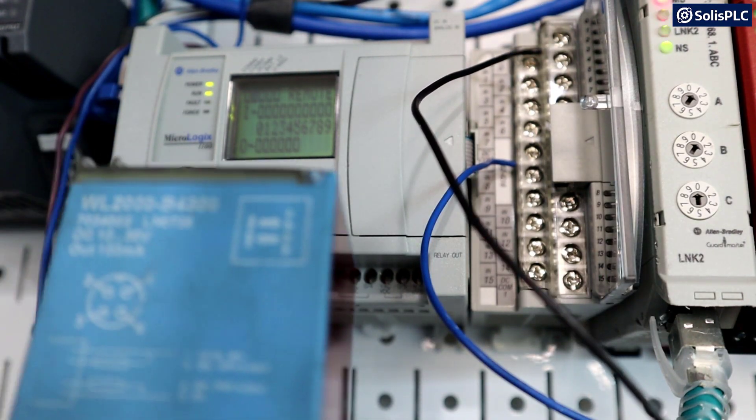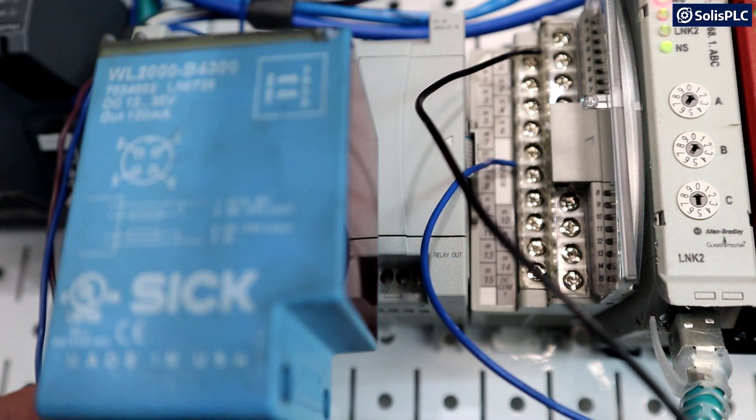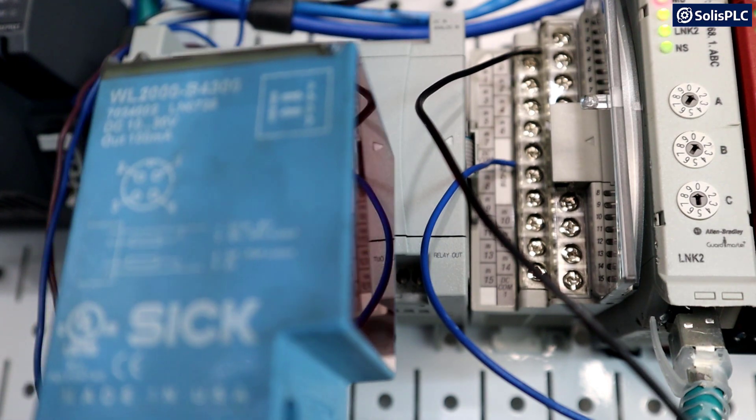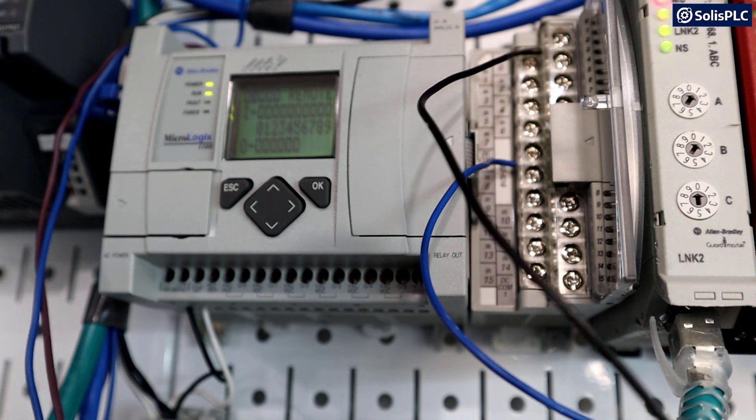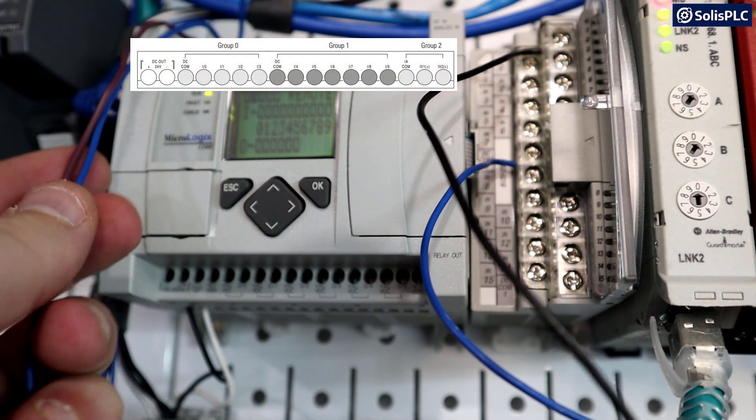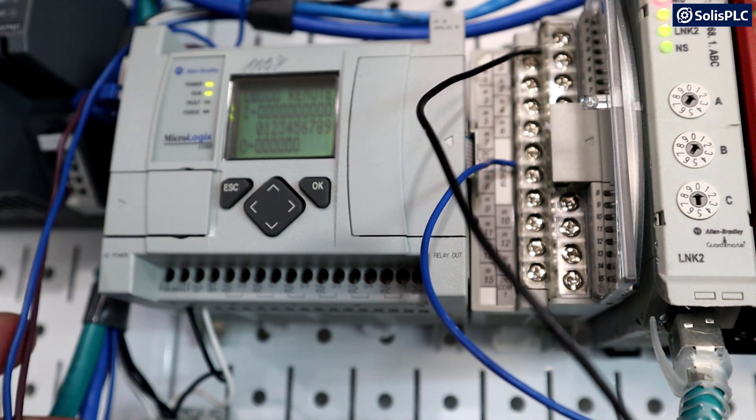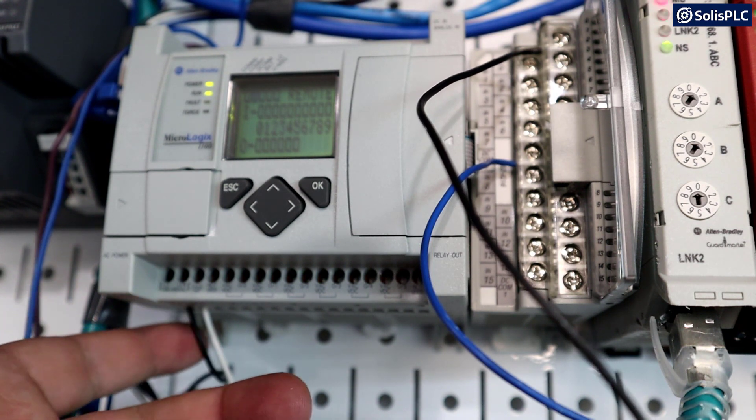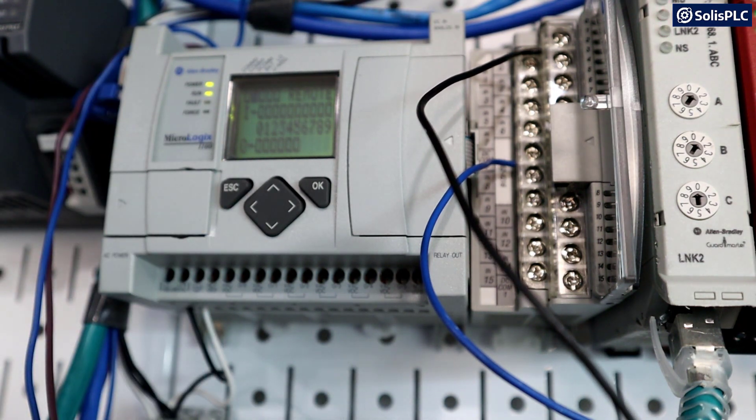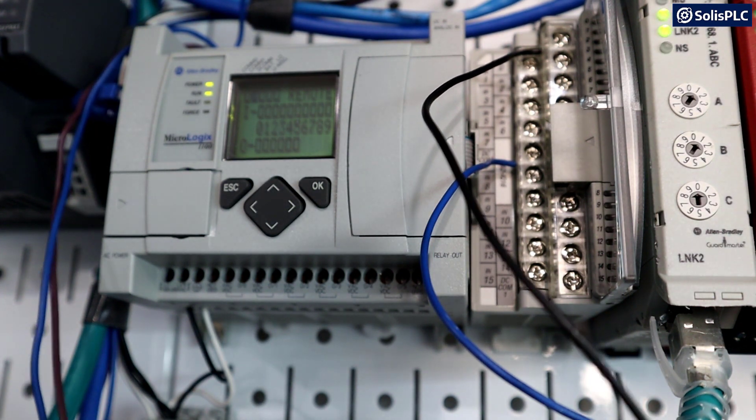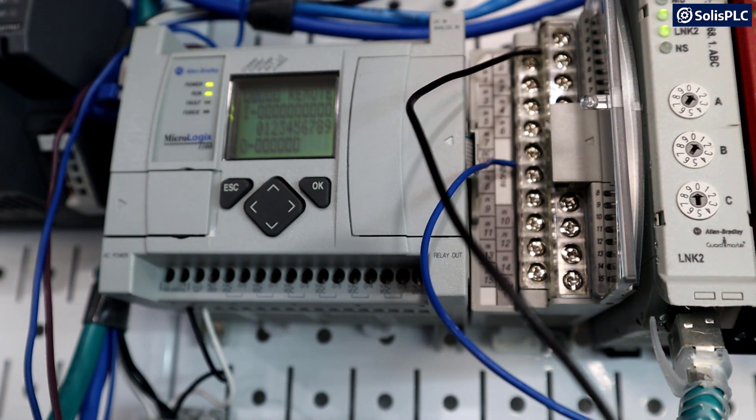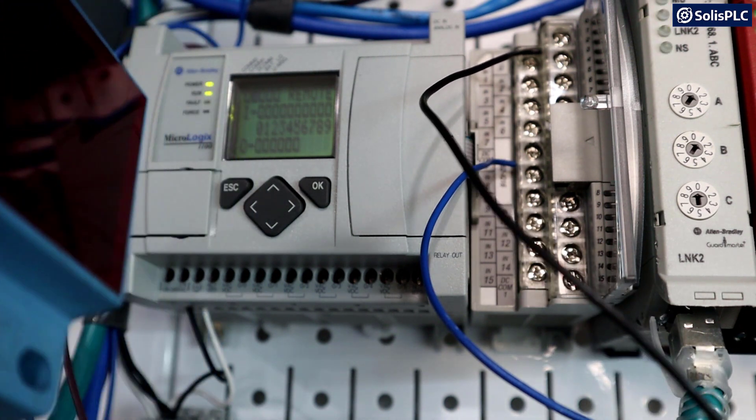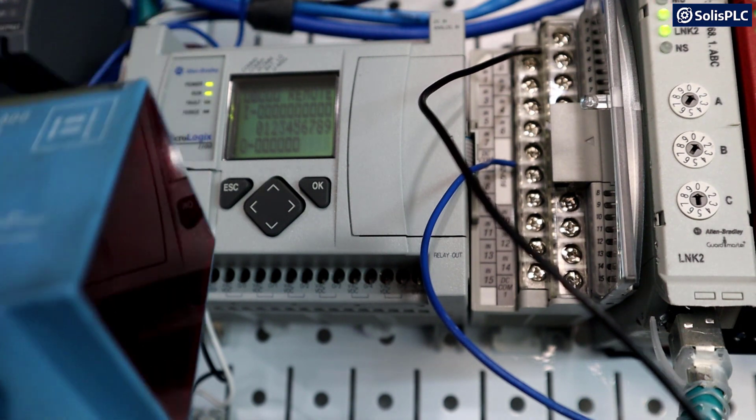And then last but not least, the power for the sensor is going to be on brown as well as blue with brown being plus 24 VDC and then blue being the ground. Those are conveniently placed on the top of the MicroLogix 1100 series PLC, which has those outputs provided. Essentially what those, where those are coming from is an internal power supply that's going to regulate the 110 from the bottom that comes in here. And then it provides you a way to power some of your sensors. I don't necessarily recommend powering a lot of them, but you can power a couple and the voltage or the current ratings are going to be in the data sheet.